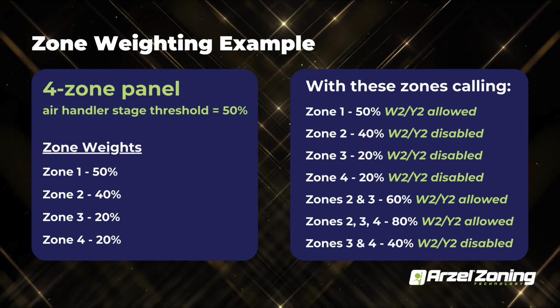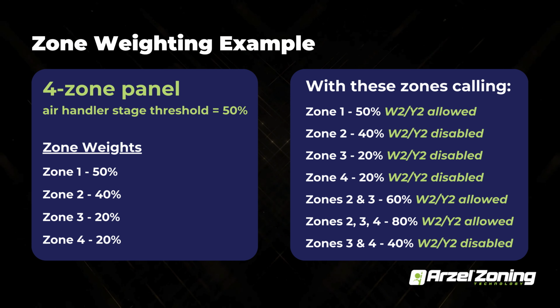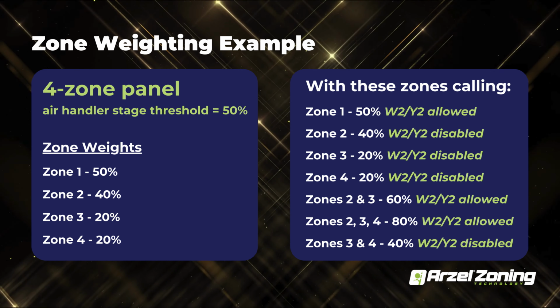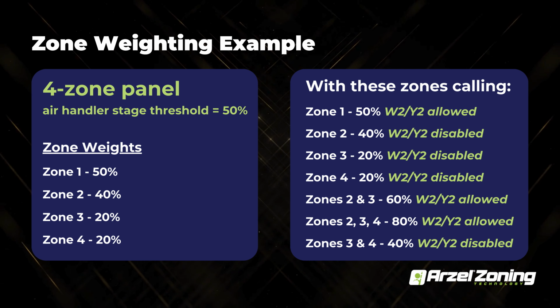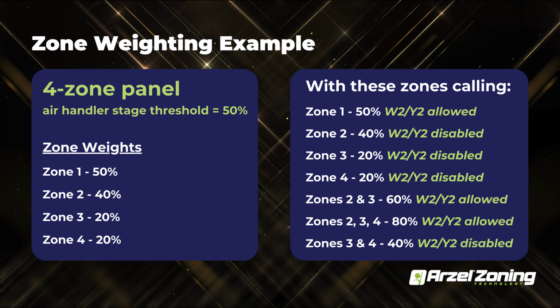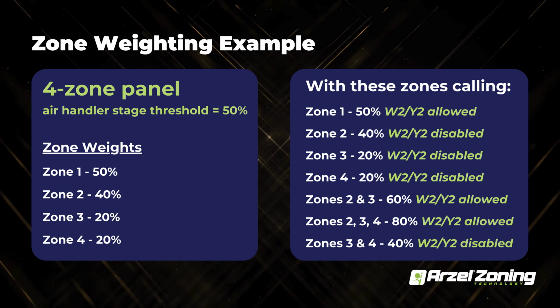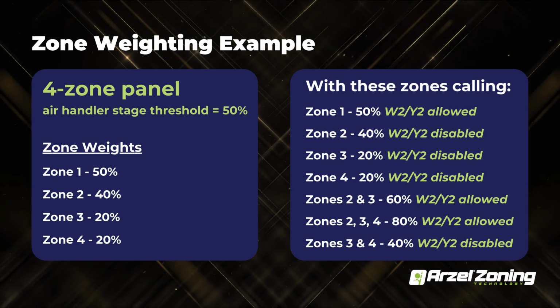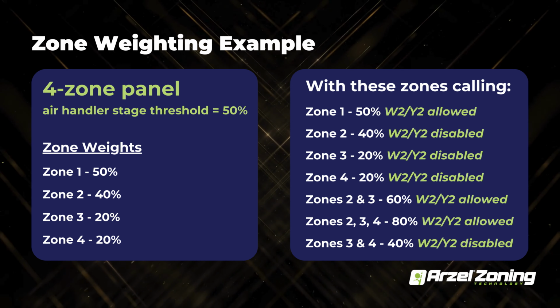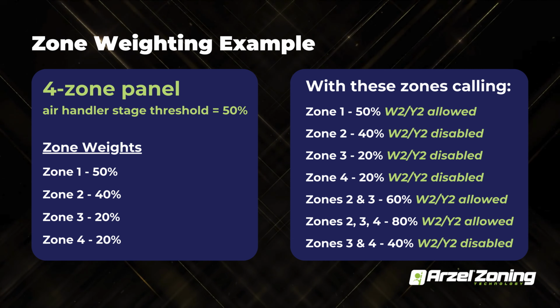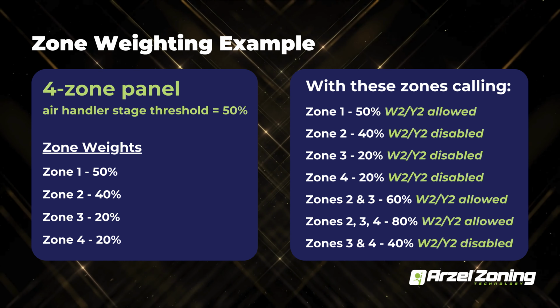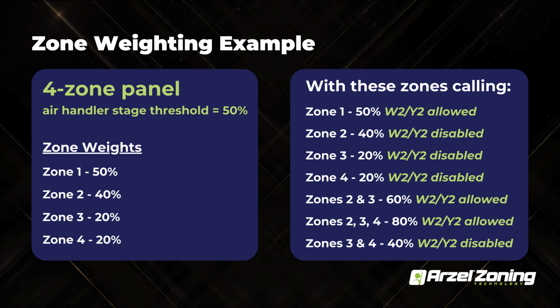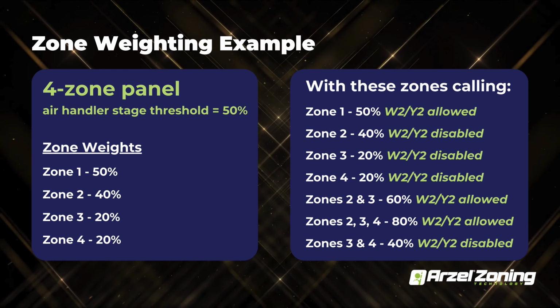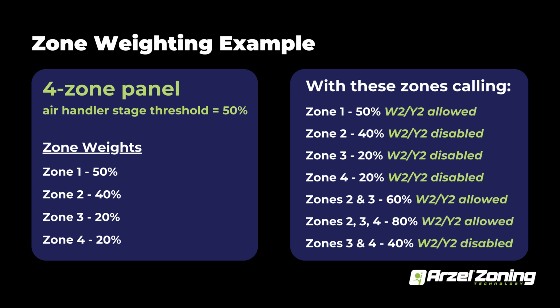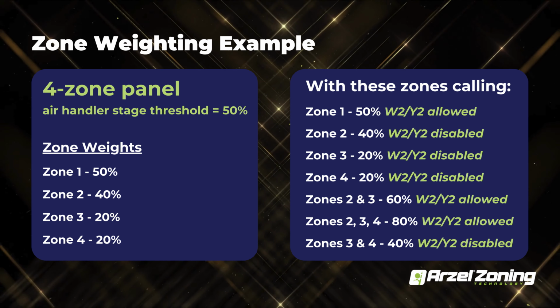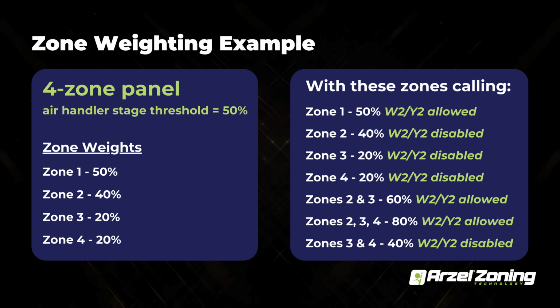So for the first example there on the left, you've got a 50% air handler stage threshold. When you look at zone 1, the weight is set to 50%. So on zone 1, you're going to be able to allow first and second stage output by itself. When you go over to zone 2, you've got a 40% zone weight. So if this zone was calling by itself, it will not be able to go into second stage operation at all. It would rely on one other zone, and it could be any zone in this panel, to call with it to equal that 50%, and then it'll allow for second stage operation.